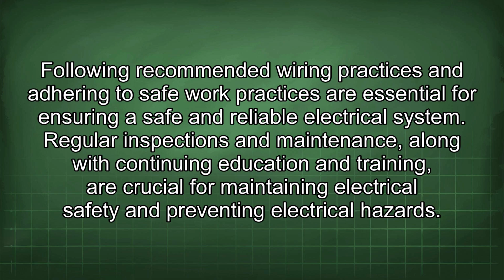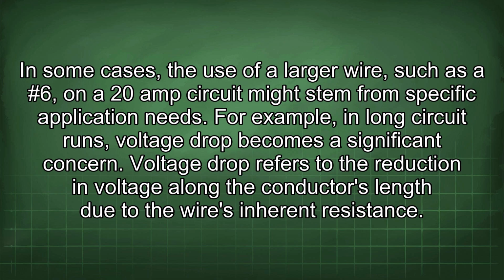In some cases, the use of a larger wire, such as a #6, on a 20-amp circuit might stem from specific application needs. For example, in long circuit runs, voltage drop becomes a significant concern.